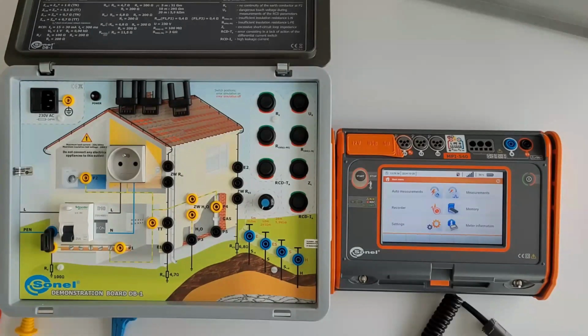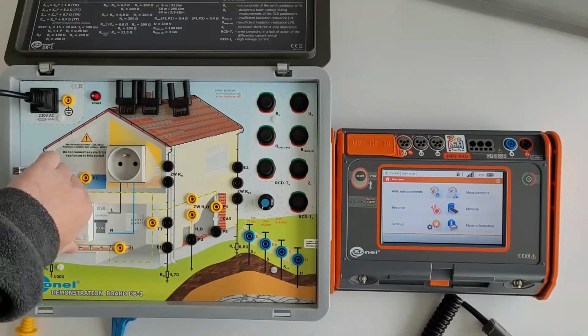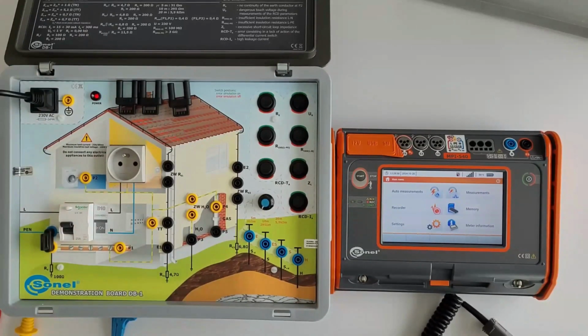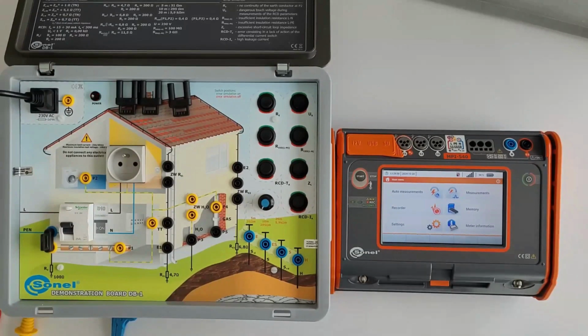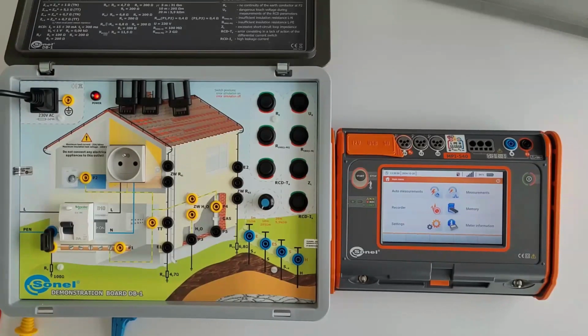Next, loop impedance, protection by automatic disconnection of supply. We measure the loop impedance and check if the condition for the automatic disconnection is met. With the configuration terminals, we can show the difference between the results. Here I show you the difference between measuring the loop impedance in the TN system and the TT system, and how we can check what kind of earthing system is in our installation.